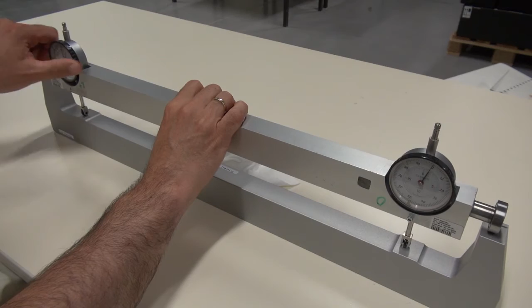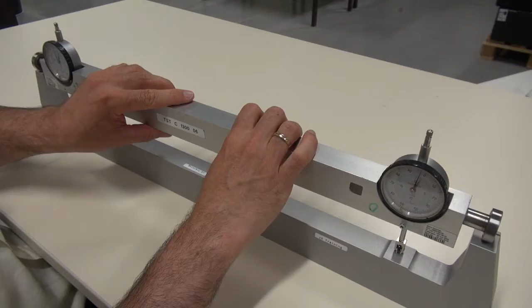When this is done, you turn the calibration tool the other way around and check once more to see if you get the same values, 0 on both sides, on this side and on that side. If that's the case, then this tool is calibrated.